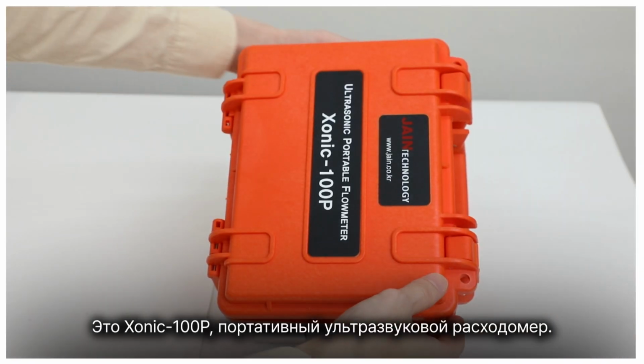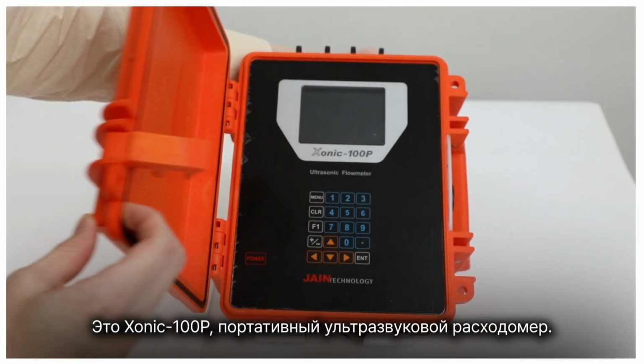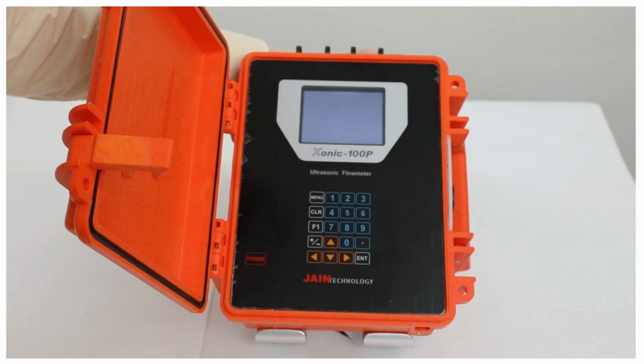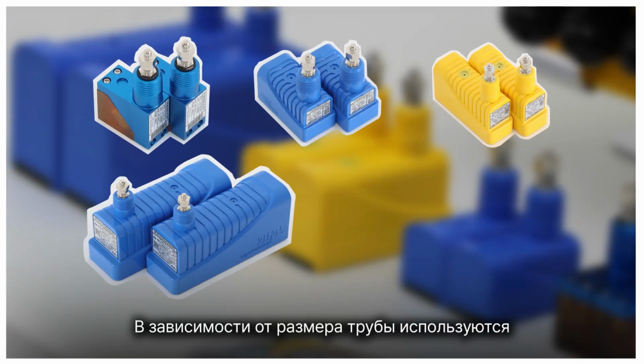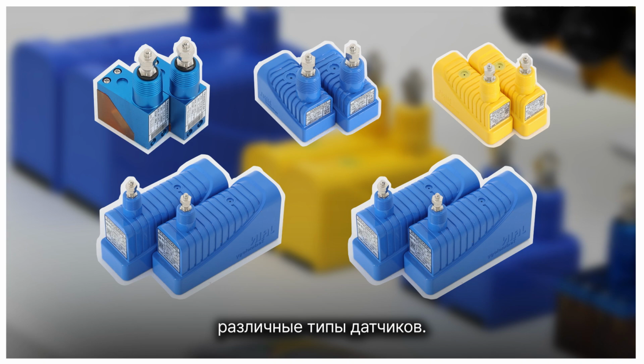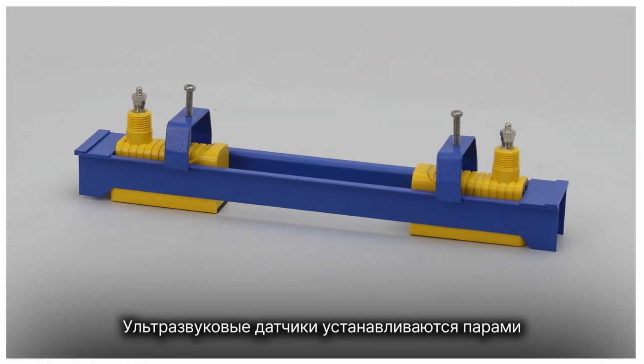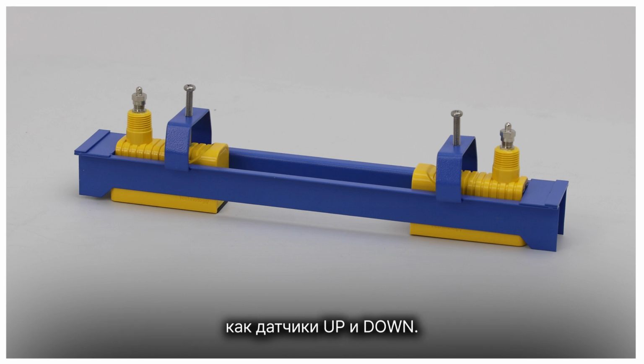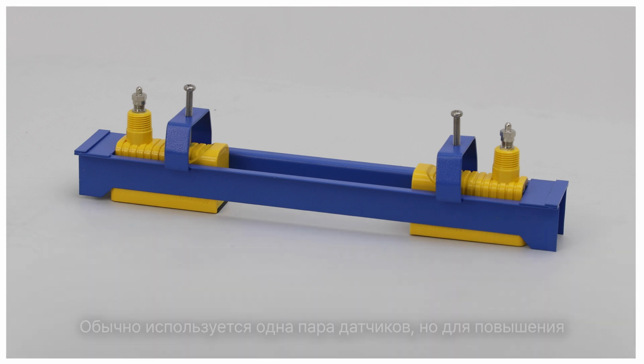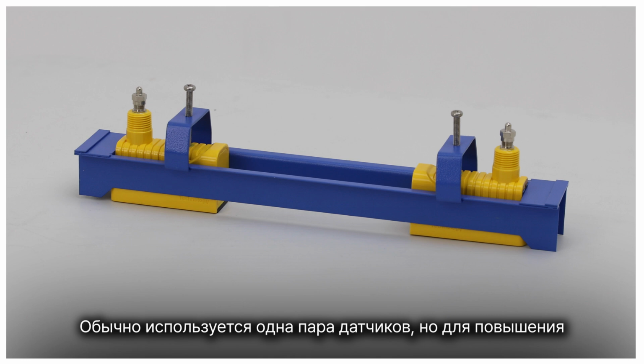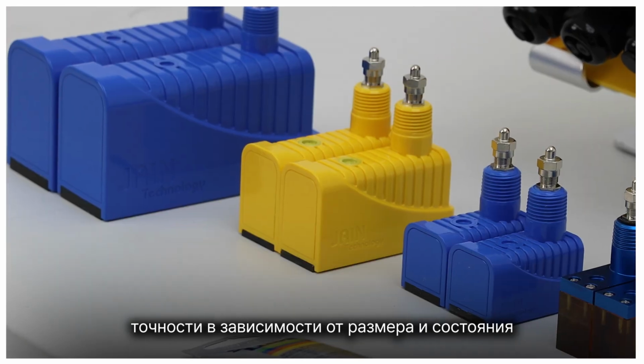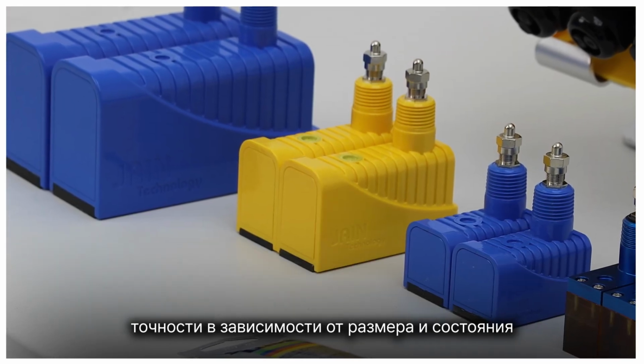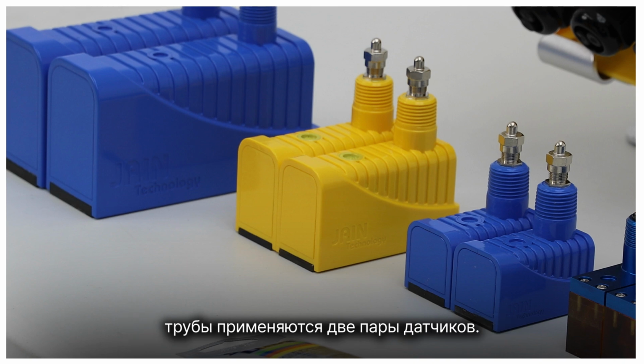This is the Xonic-100P, a portable ultrasonic flow meter. Different types of transducers are used depending on the pipe size. Ultrasonic transducers are installed in pairs as up and down sensors. Usually, one pair of transducers is used, but two pairs of transducers are applied for higher accuracy, depending on the size and condition of the pipe.